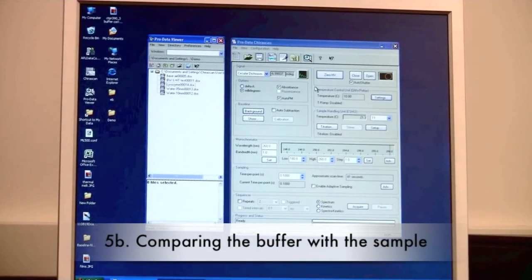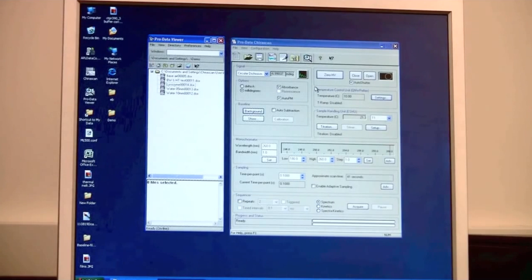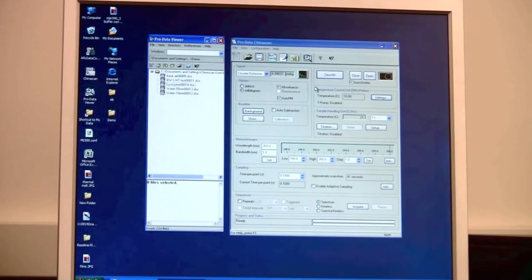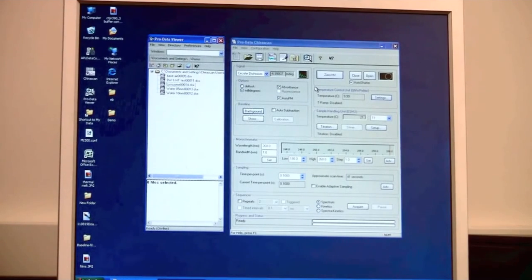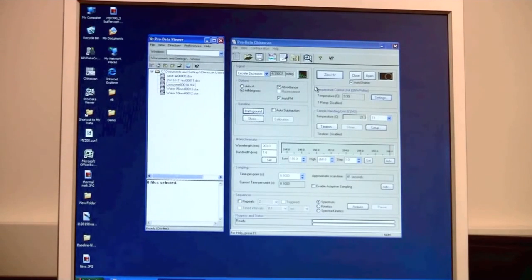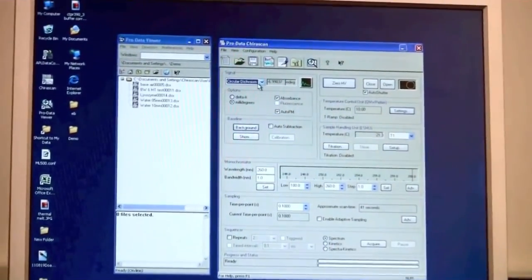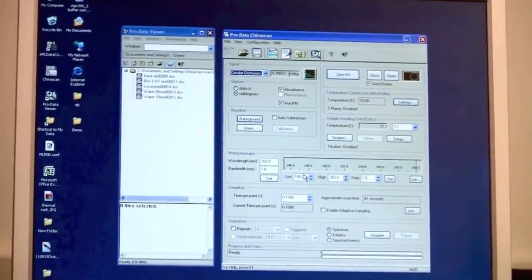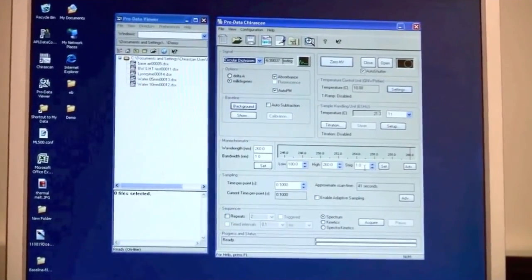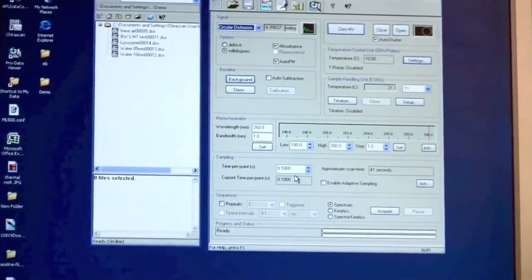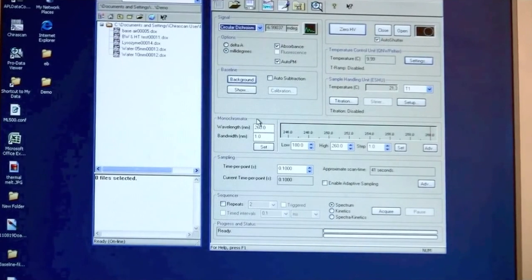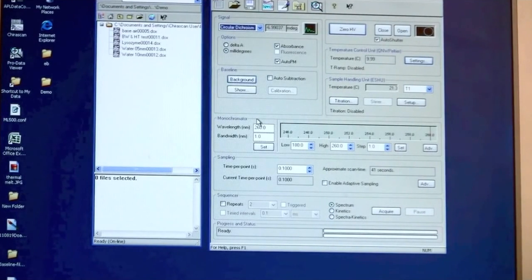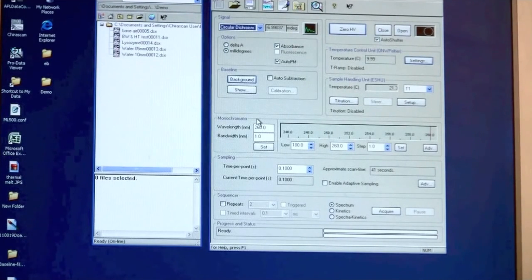So after I have been looking at the two different path lengths I have decided that using the shorter path length might be the best option for this experiment. I then would like to investigate how my buffer compares to my whole sample. And for doing that I first set up the software to use CD instead of absorbance. I will cover the same range as before over the same time frame. And then what I will do is that I will collect the background against nothing. And I will then collect a trace of the buffer and then a trace of the sample.